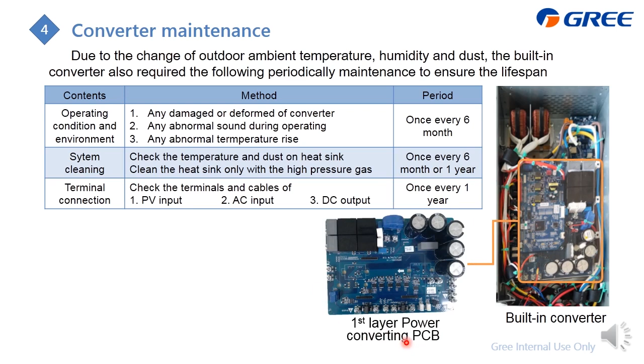So you can find it is a little bit complicated, and if your working condition is not that good, you also need to do the maintenance. Based on the situation, which is the condition, this outdoor unit located here has our recommended period. And if your working condition is not that good, you may need to shorten this time. And here are the checking items. During the VRF being on, here is how to check it. Check for damage or deformation of this converter, or any abnormal noise coming out or abnormal temperature rise.